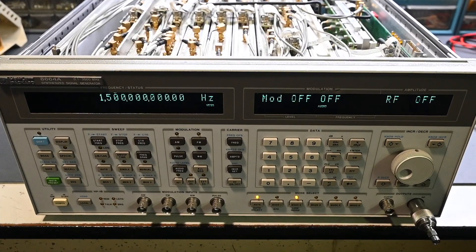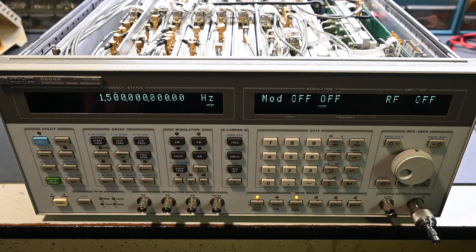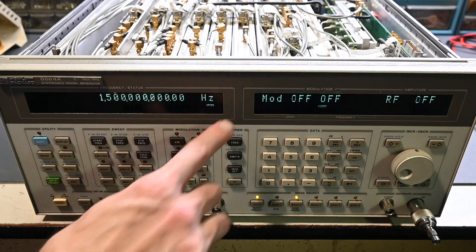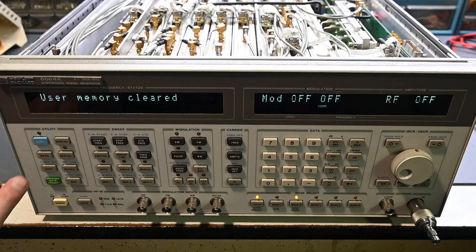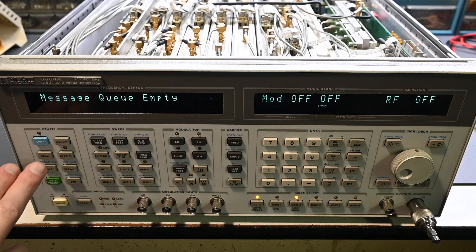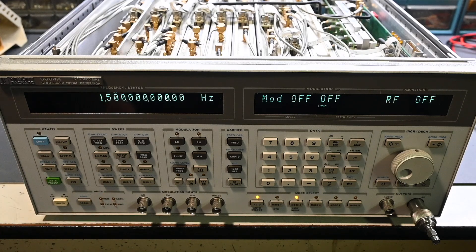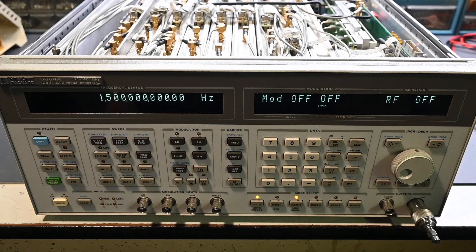All right, the calibration routine has finished, and this is the display that came up, so it just says message. So if we go right here to message, yep, user memory cleared, that's normal. Message queue empty, perfect, no error messages, everything is looking spot on, so it looks like the firmware is upgraded with no problems.